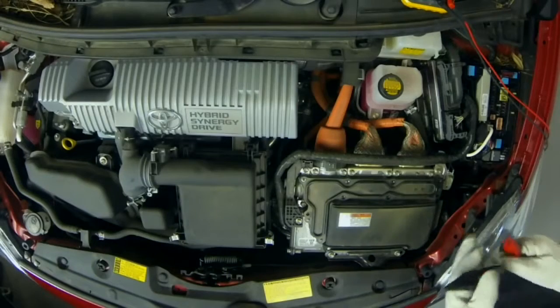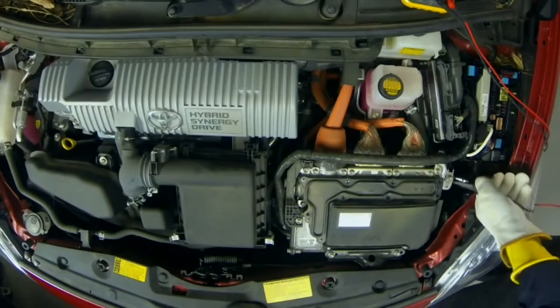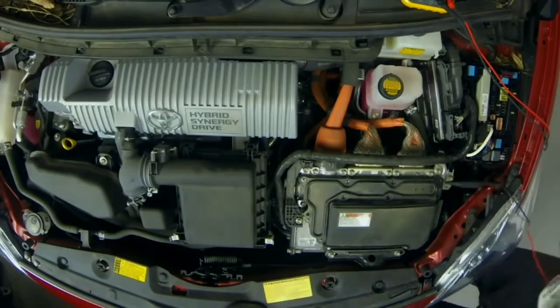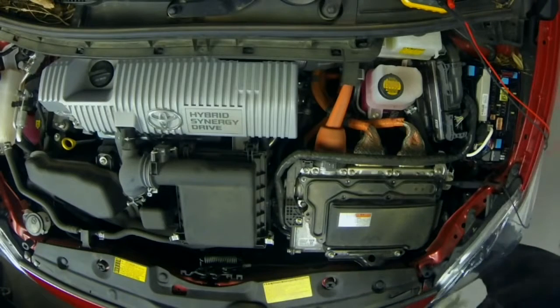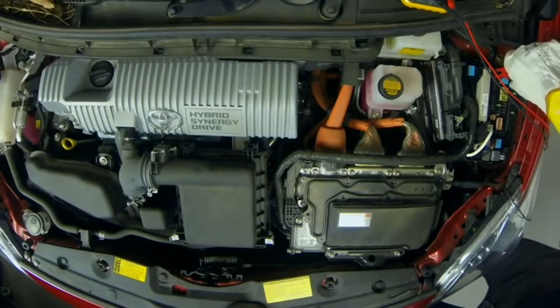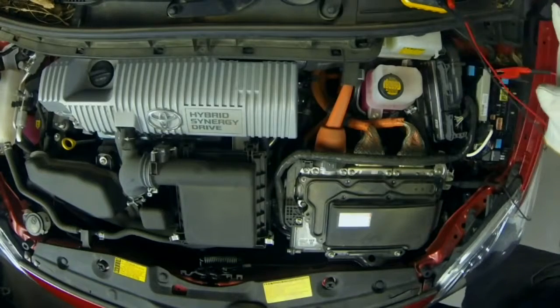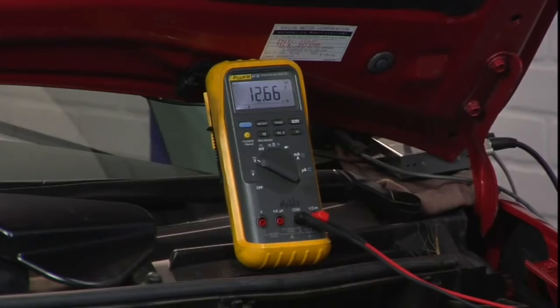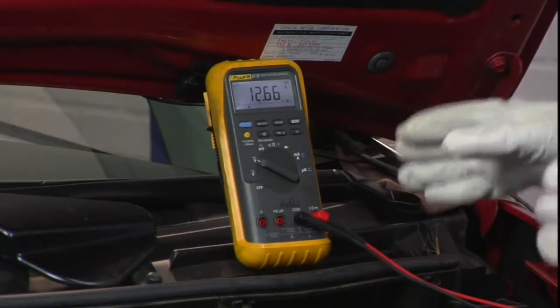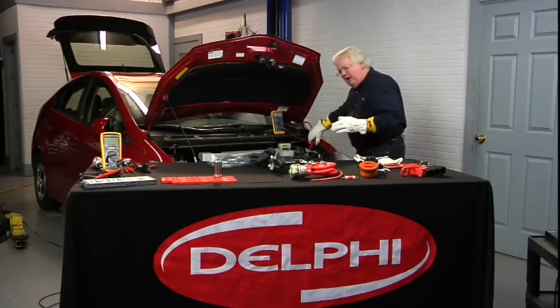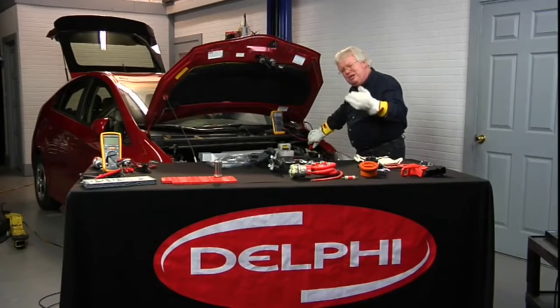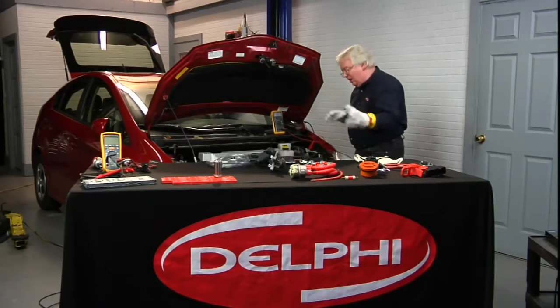So what we'll do is get a known good ground, and go to something we know is good power, like this jumper bar on this bus electrical center. If we see 12.5 volts, we know the meter is working. We don't have an auto ranging issue, a connection problem, or a fuse issue causing the meter to not function and show 0 when it needs to be showing live voltage. So 12 volts is fine, that's harmless.